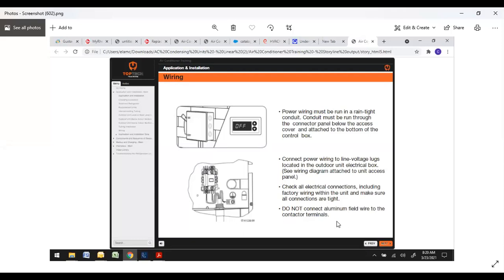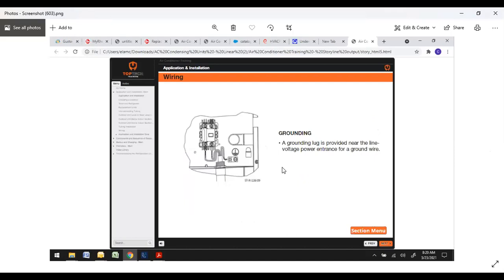Do not connect aluminum field wire to the contactor terminals. It's been a long time since I've seen an aluminum wire out to a house, but do not connect aluminum field wire to the contactor terminals. Obviously, grounding is important in the unit right here. Next to your contactor, there is a grounding lug provided near your line voltage power entrance for a ground wire. Make sure that you utilize that.